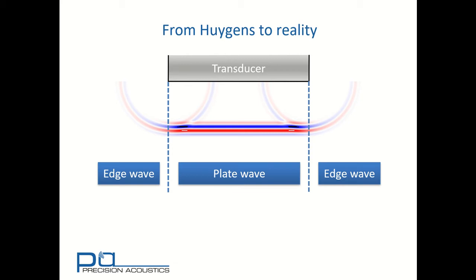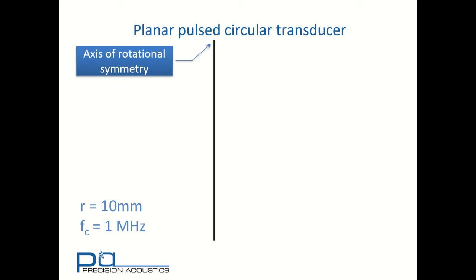But to start off with we'll look at an animation of a pulsed transducer with a short signal. As we discussed in the introduction for simplicity we'll consider 2D representation only. So this particular transducer of radius 10 millimetres and centre frequency of 1 megahertz has an axis of rotational symmetry. We're looking from R equals 0 to R equals 40 millimetres in the simulation. Here we can see the edge wave radiating out along with the plate wave.